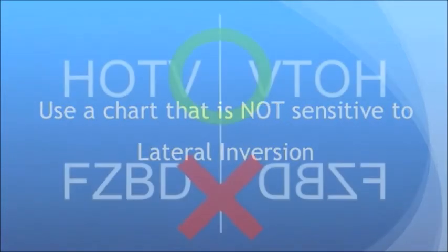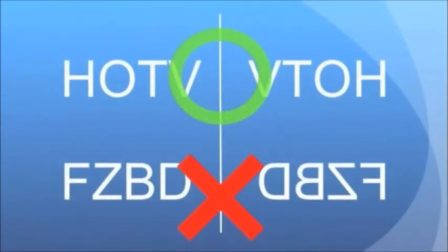For this setup, you will need to use a chart with an optotype that is not sensitive to lateral inversion. This means letters like H, O, T and V are acceptable, while F, Z, B and D are not.